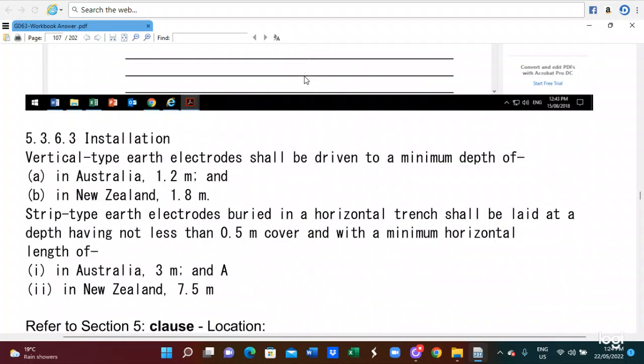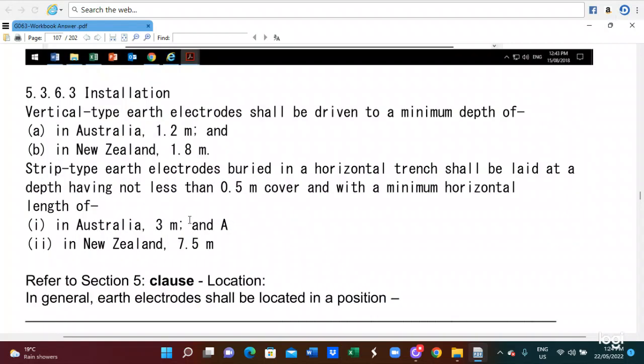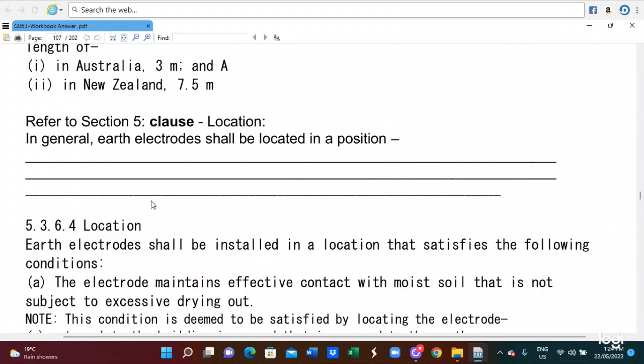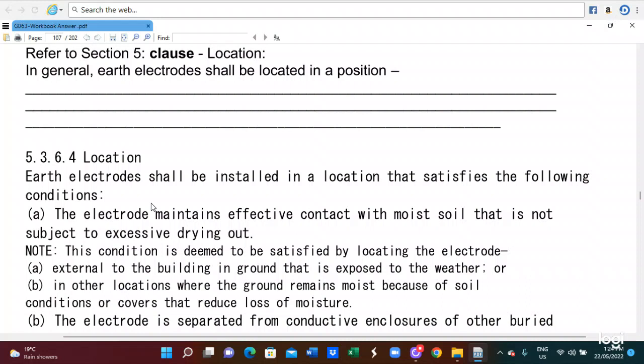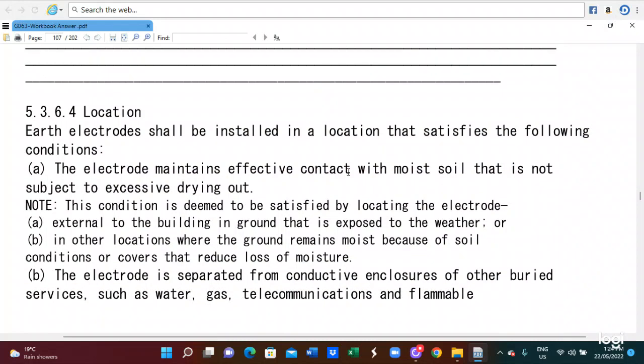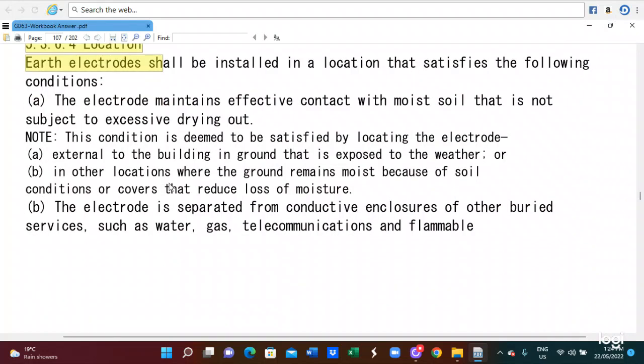5.3.6.3 is installation. So this is for the installation of the electrode. You can see in the Australia and New Zealand standard the electrode site location. The earth electrode shall be installed in a location that satisfies the following conditions. So the earth electrode locations you can read there, plus 5.3.6.3 and 5.3.6.4, the location regarding the earth electrode installation.